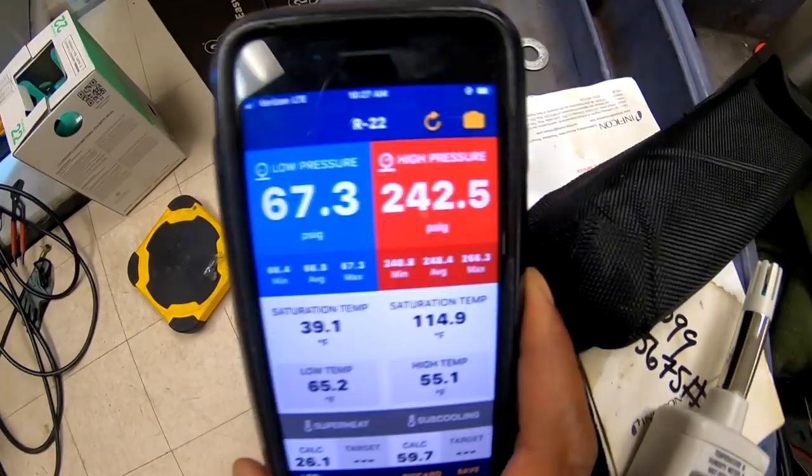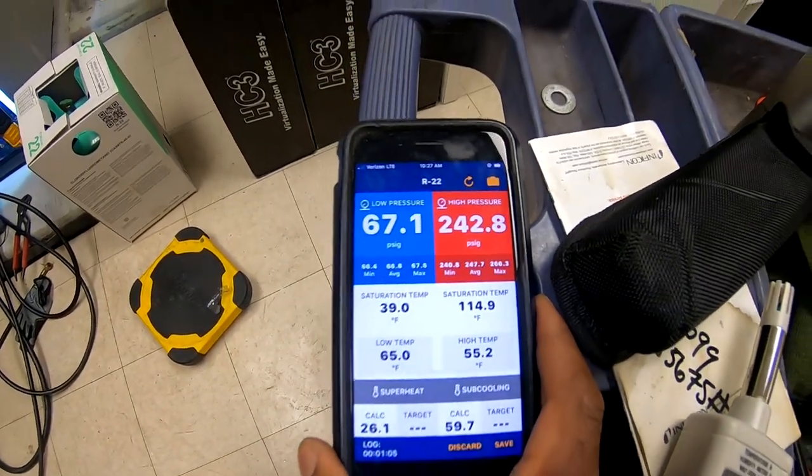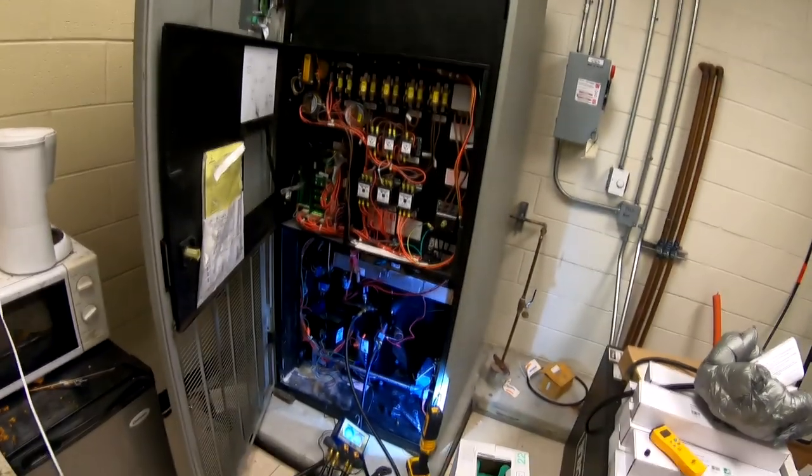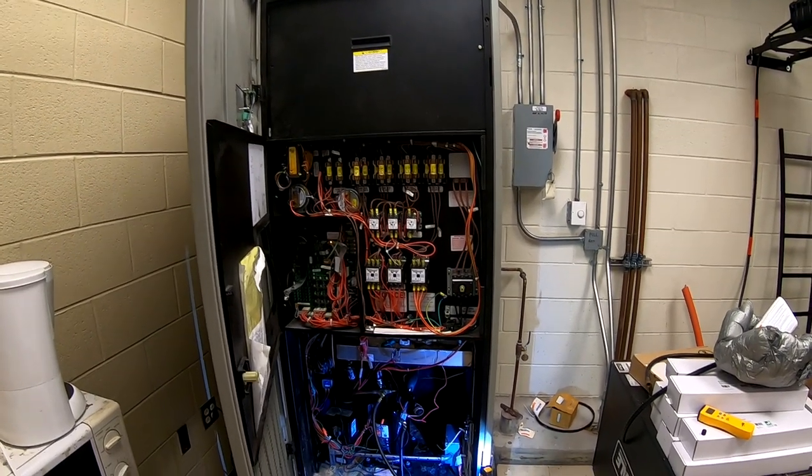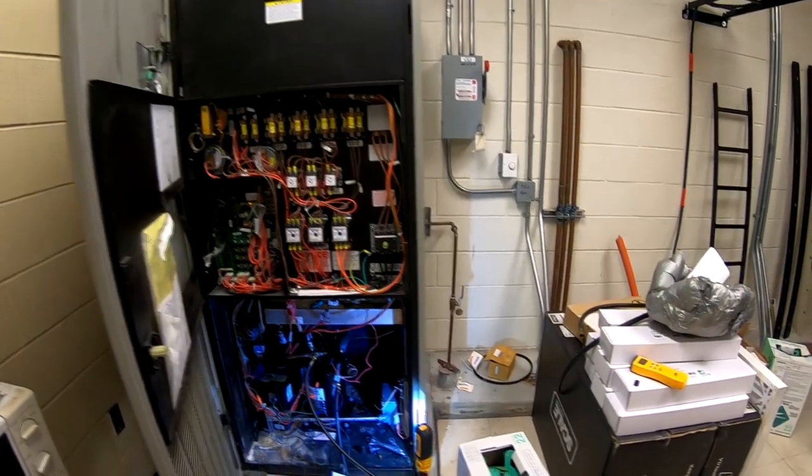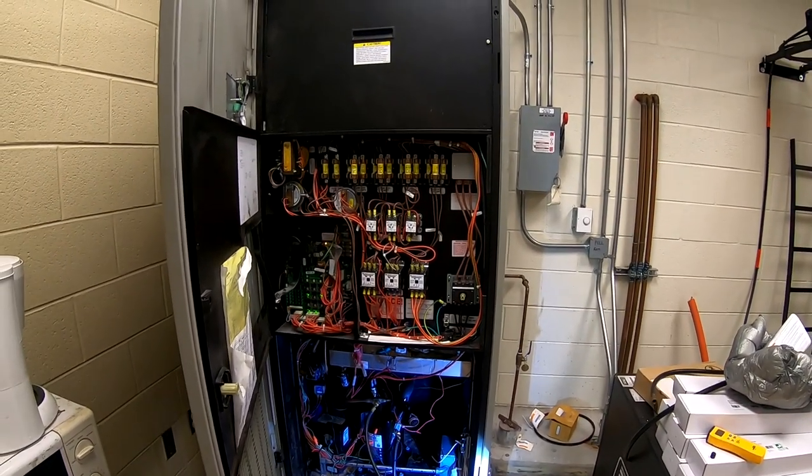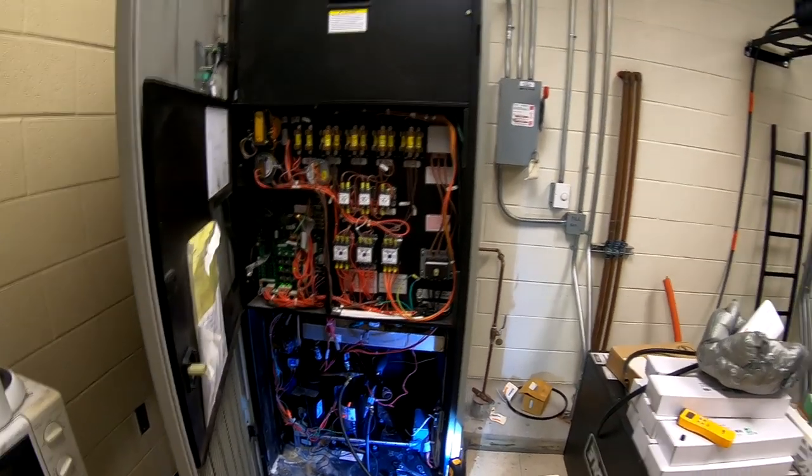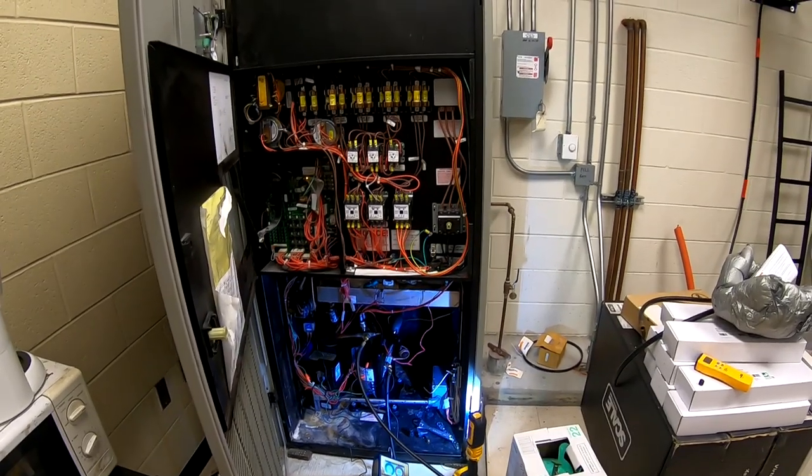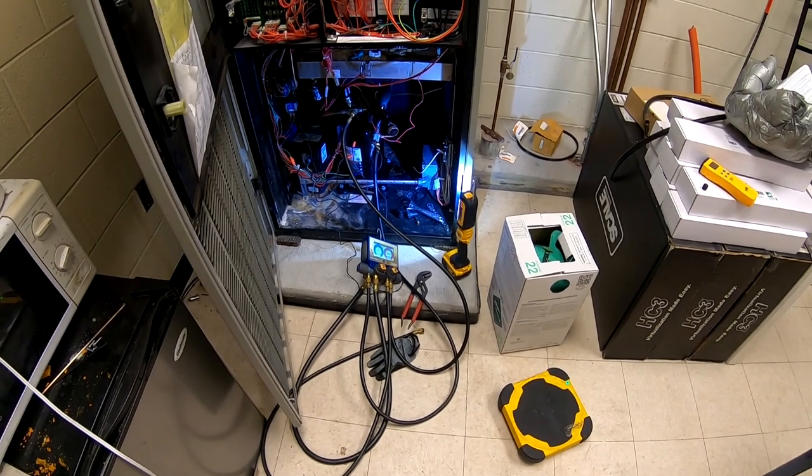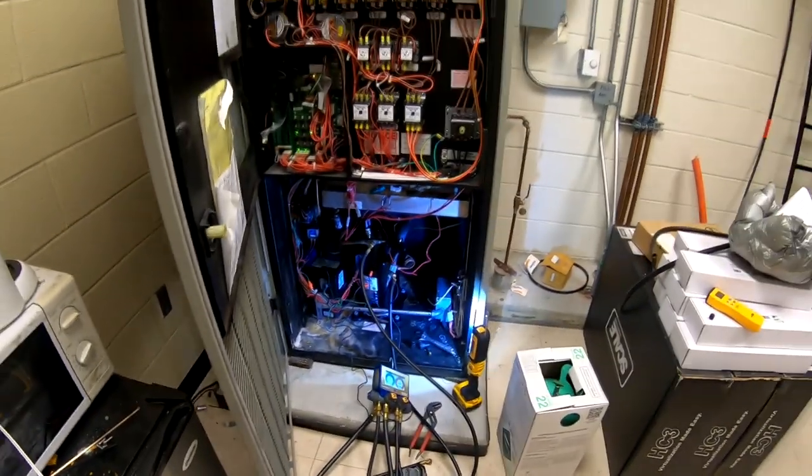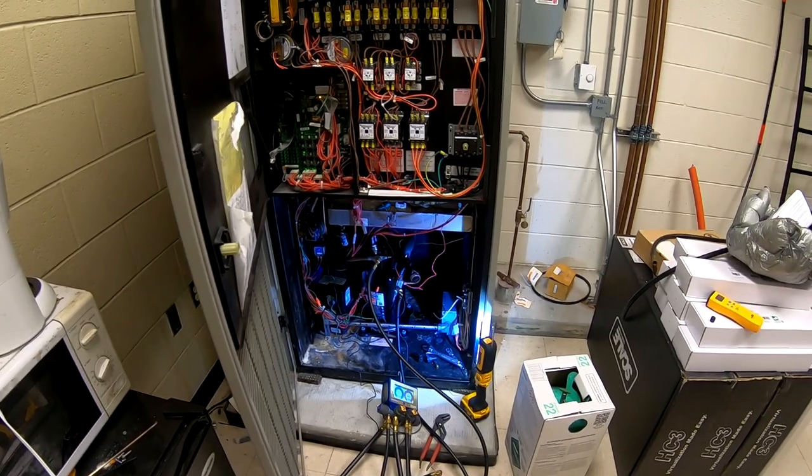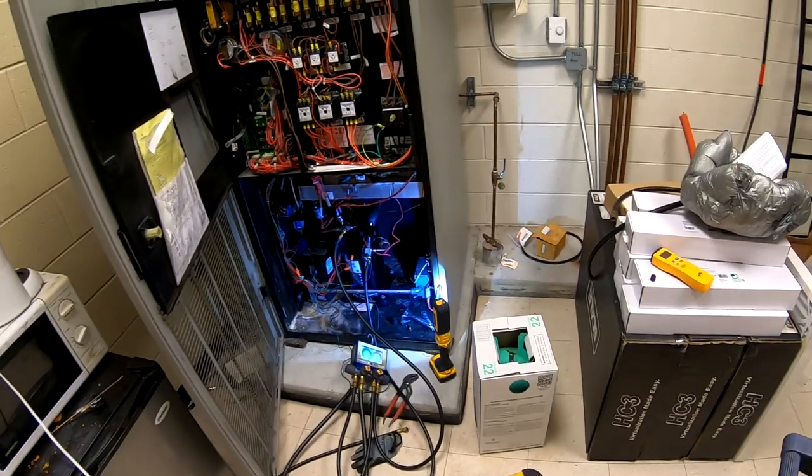Alright, everything looks good. I'm gonna get a target superheat. But I just spoke with the customer. I said when the other company came and replaced the compressor, the outdoor fan motor was bad also. So everything looks good. I verified that the outdoor fan was working. So I am going to call it good, just write all the refrigerant pressure down. I'm doing basically a startup on it - check all the supply temperature, check the compressor, compressor amperage, check the blower motor amperage, and we're gonna wrap this one up. I'm gonna request that he do a maintenance on it, clean out this humidifier pan, and we should be good to go.